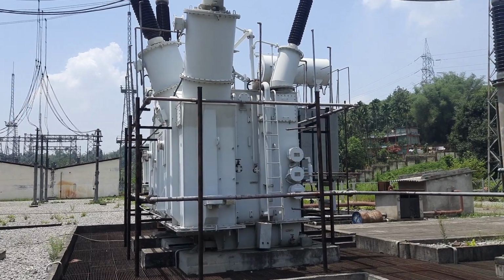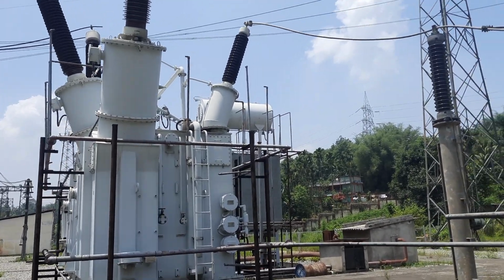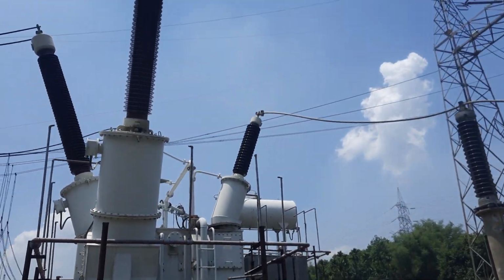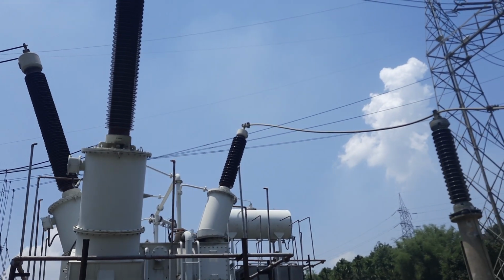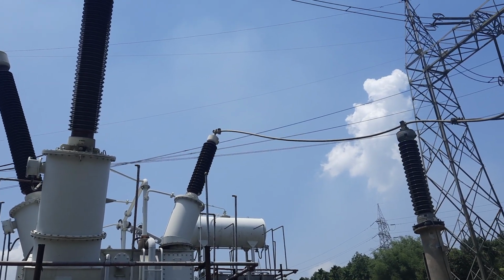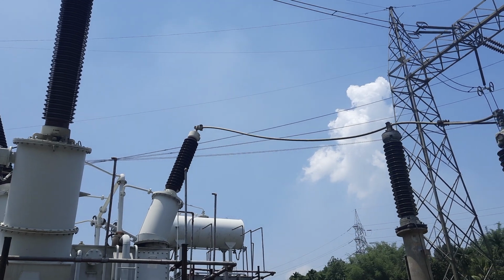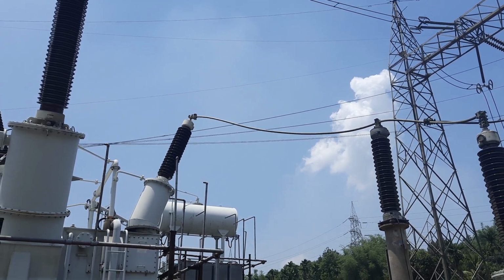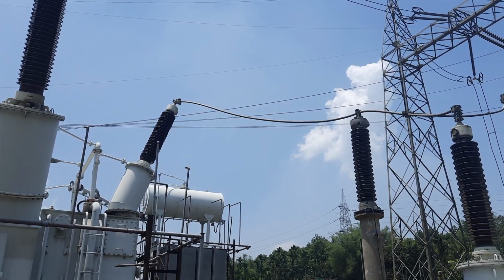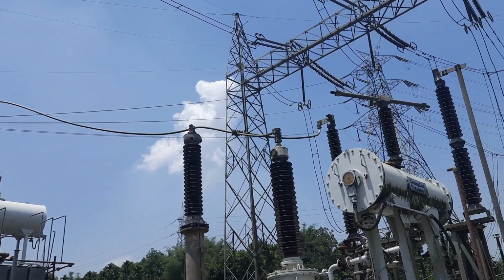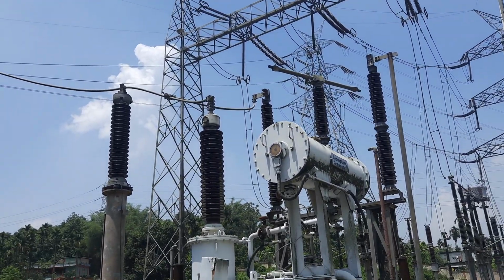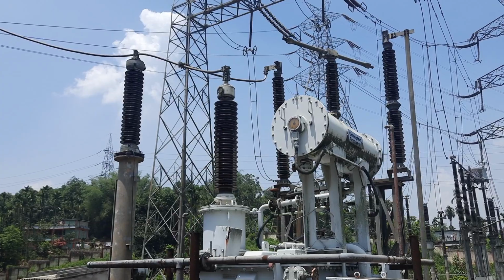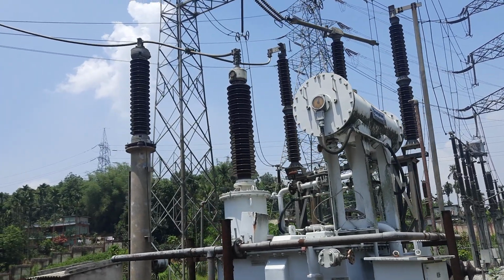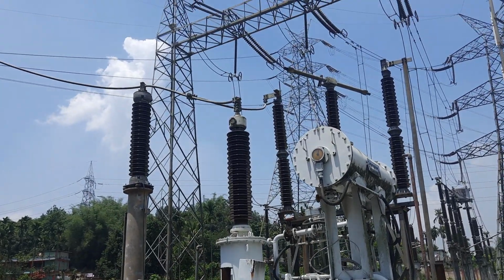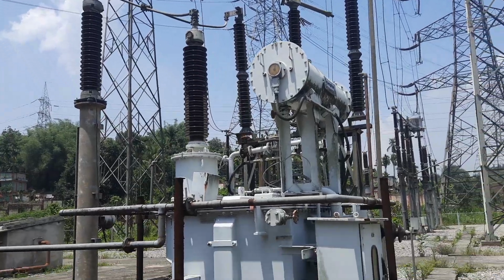And the neutral of this, as you can see, is because for a balanced system ideally the current should be zero, but practically it may not be possible to have zero current in the neutral. We have to ground this neutral, and we are not grounding it directly, we are grounding it through an NGR, a neutral grounding reactor. So it is grounded through this NGR.